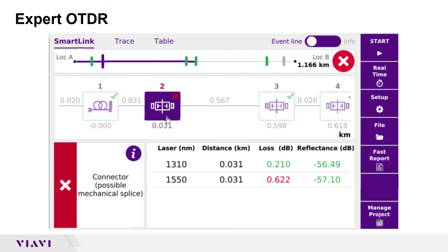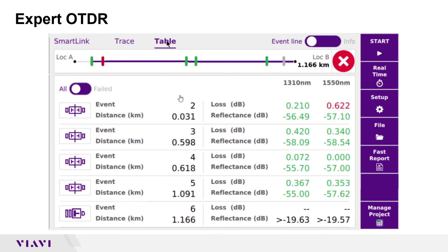The third display option is table view. In table view, distance, loss, and reflectance are shown for each event. Values that violate loss or reflectance pass-fail thresholds are shown in red. You can tap the toggle switch to display all events or just failed events.